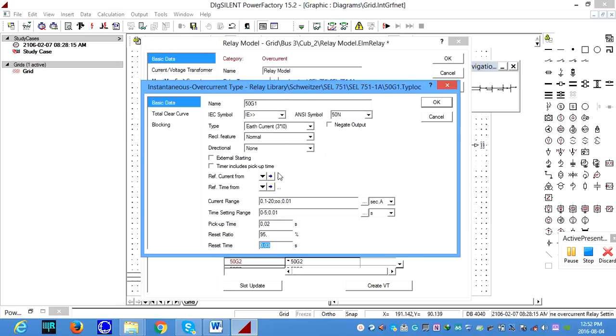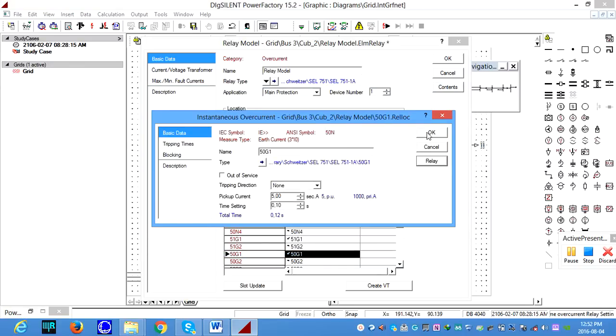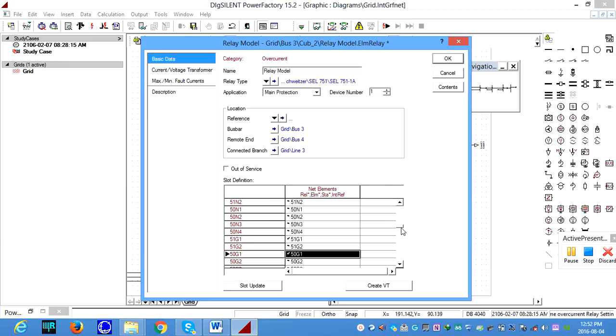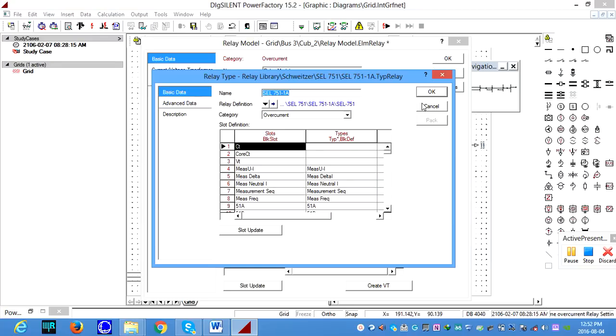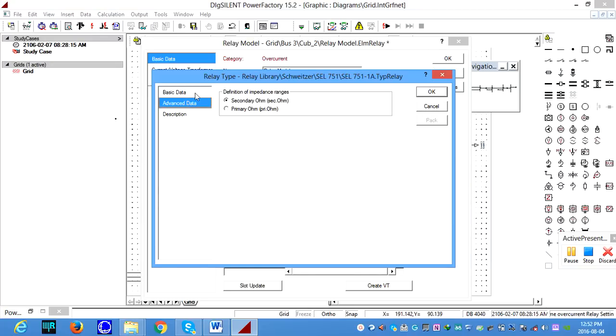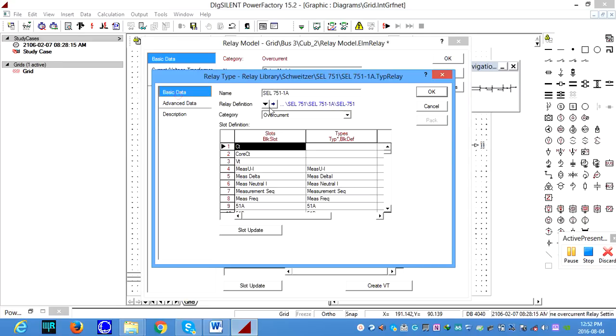But if you want to play around with the settings, make sure, if necessary for the specific location of the network, you are more than allowed to change any settings here. But the first thing is we need to understand the settings in the relays. I think the first experiment is just preliminary knowledge to explore the protection settings for the overcurrent relay. So when you have mastered the protection settings, then you can go around and play with the relay and change the settings. Also, you can make the settings in terms of secondary or primary ohm values and so on. But again, I strongly recommend that once you have mastered the settings of the relay, then you're more than welcome to play with different settings.